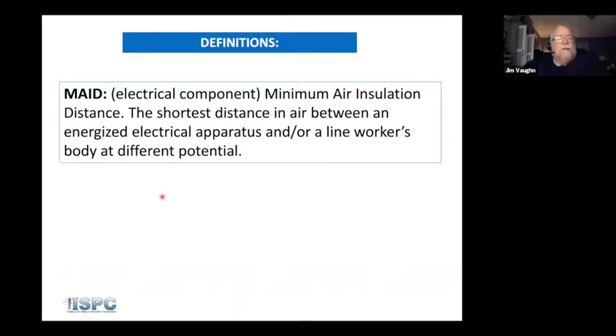So let's look at some definitions here. And I mentioned this earlier, so I want to tell you what this is. MAID, M-A-I-D, is the electrical component of MAD. This is the air distance necessary to prevent flashover to the nearest potential that would be in or close to the conductor. Now, if you're a gloving lineman, you know that you can take a pair of Kleins and move it toward the phase. And when you get about 3/4 of an inch away or 9/16 inch away, the phase will arc over to your Kleins. That's a lot of fun. I used to chase and electrocute spiders that way in pole tops, but that's another story. That is associated with MAID.